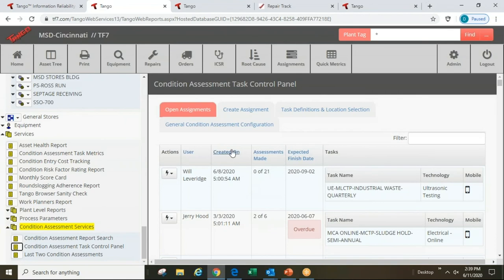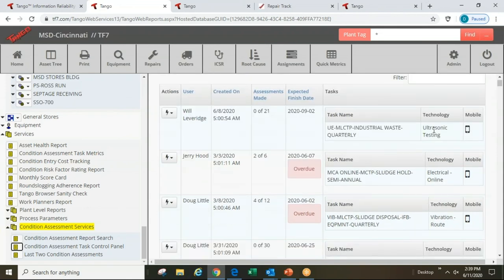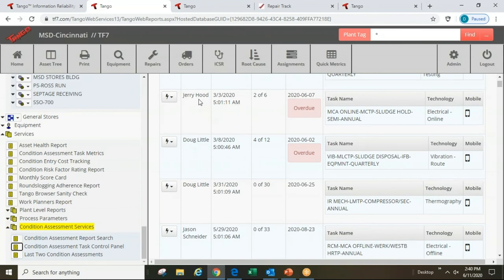Here we see that one technician started an ultrasonic testing task three days ago but hasn't assessed any of the 21 items yet. There's an electrical online task started way back in March where the technician has accomplished two out of six items, but it's now overdue. And a vibration route is also behind. I need to follow up to understand why these assets haven't been covered as needed.